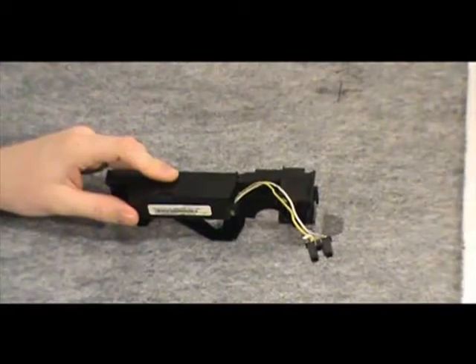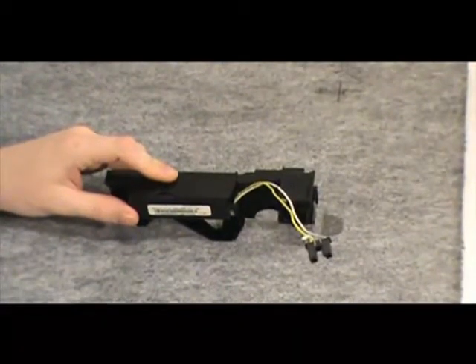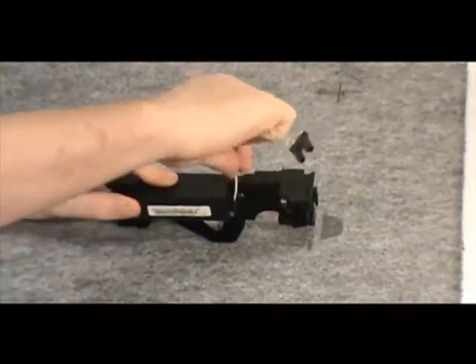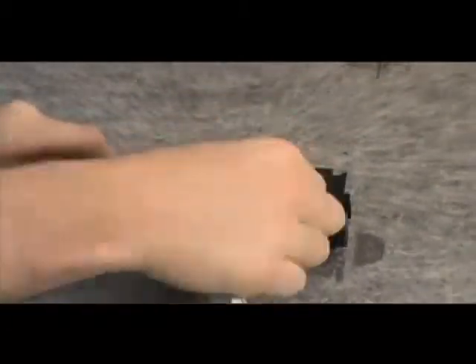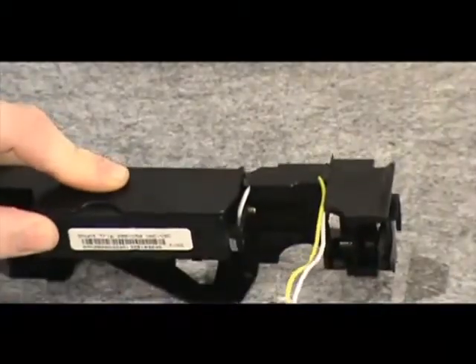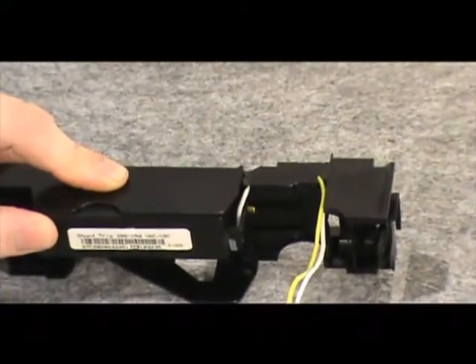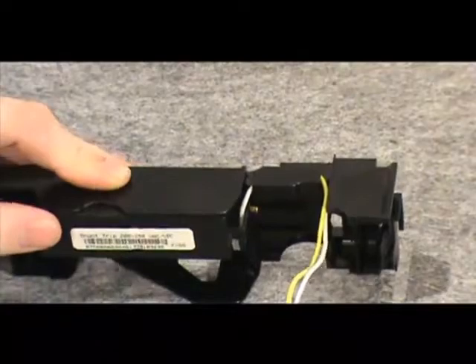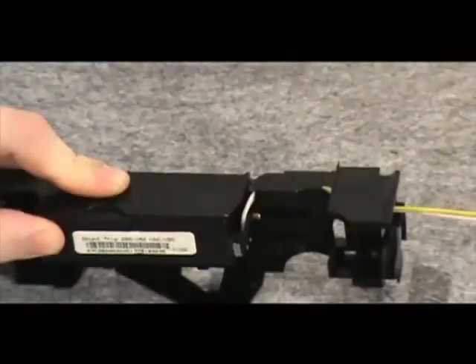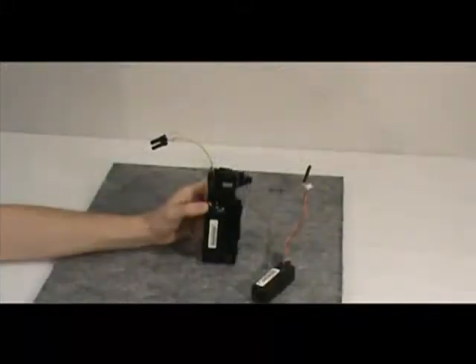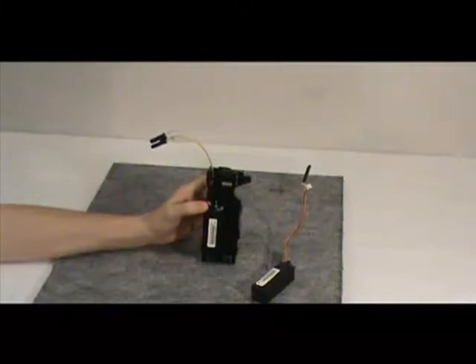Once you've attached the shunt trip to the left accessory tray, route the 2 secondary leads behind the first molded tab, then down under the second molded tab and out the end of the accessory tray. To install an undervoltage release or a second shunt trip into the accessory tray, perform the exact same process as you just completed for the first shunt trip.